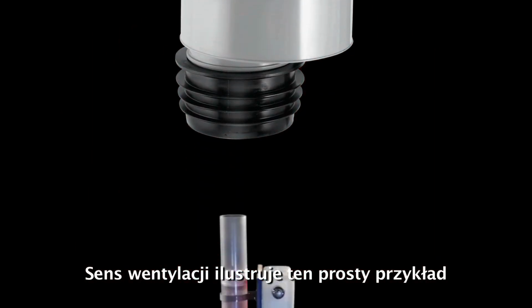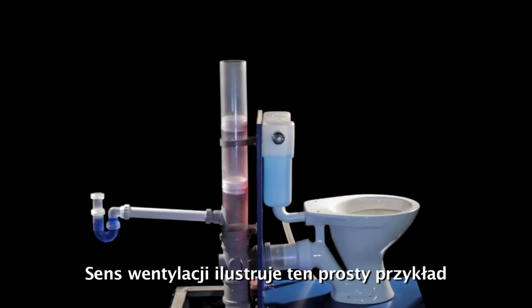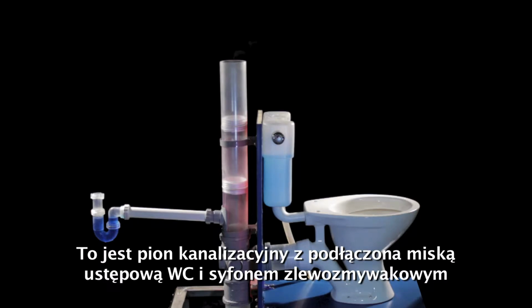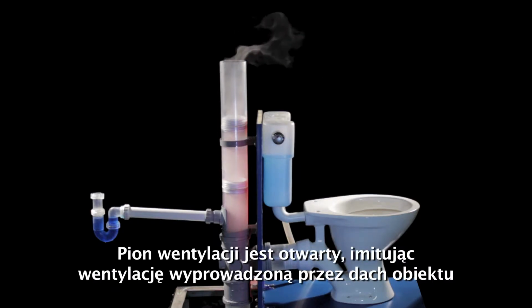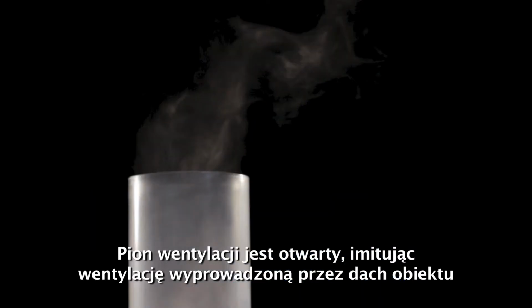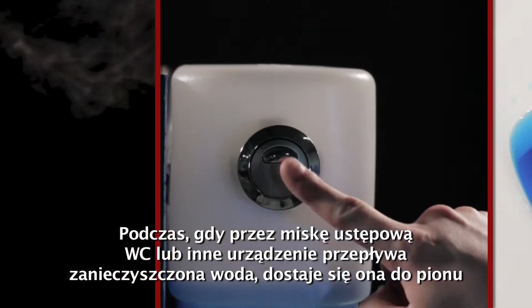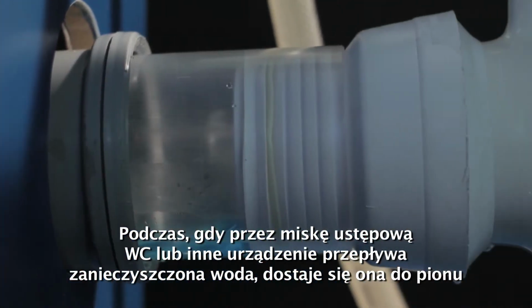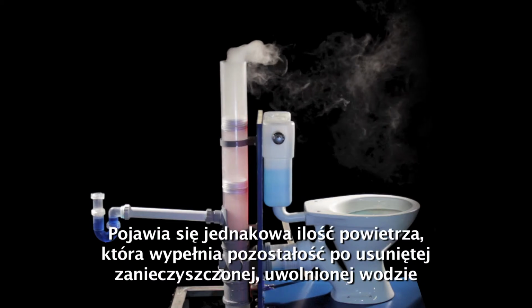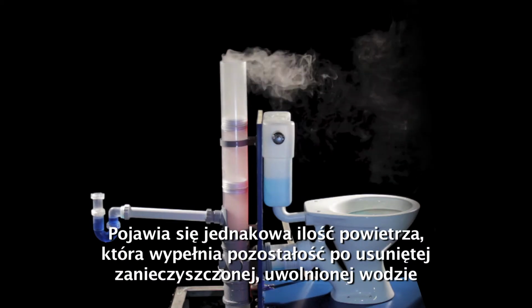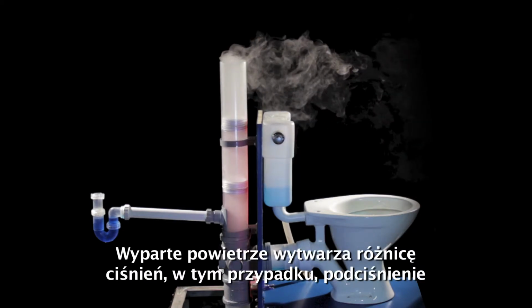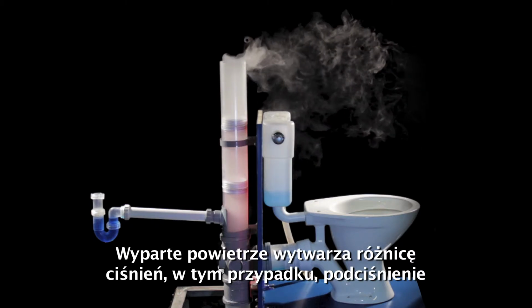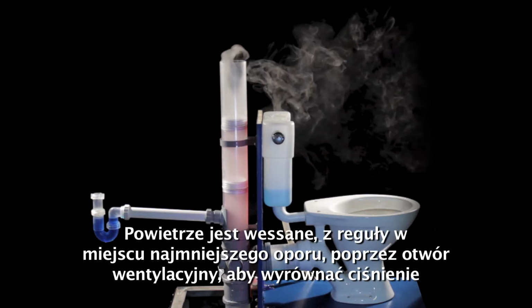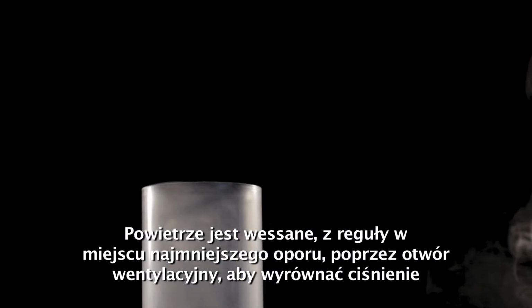The need for ventilation can be illustrated with a simple test. Here, a WC and sink trap are connected to a vertical soil stack. The stack is open to atmosphere, simulating a through-roof vent. When a WC or other appliance discharges, a volume of wastewater enters the stack. A similar volume of air is displaced to accommodate this discharge. This displaced air will create a pressure difference, in this case, negative. Air is sucked in, normally via the path of least resistance, through the vent to equalise the pressure.